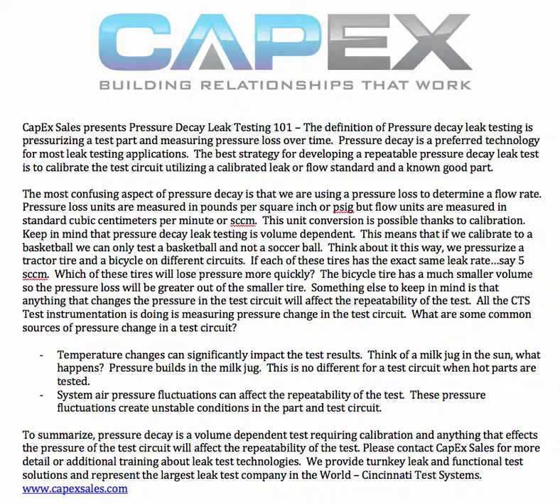The most confusing aspect of pressure decay is that we are using a pressure loss to determine a flow rate. The units for pressure are typically PSIG, pounds per square inch, and the units for measuring flow are standard cubic centimeters per minute, or SCCM. So we're converting the pressure loss with pressure decay to a flow rate. This unit conversion is possible because we do a calibration with a known leak.